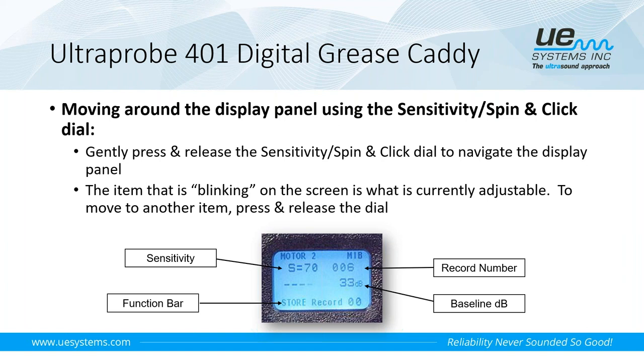Now, if we see the arrow pointing back to the left, that's telling me to turn down the sensitivity. It's telling me that the sensitivity is too high to be able to measure how much noise this bearing is generating. Either way, the instrument will tell you in which direction to turn the sensitivity. The maximum sensitivity setting is 70, and it will go all the way down to zero.